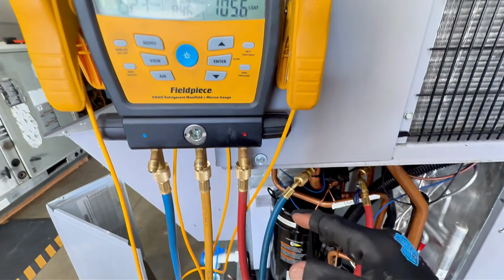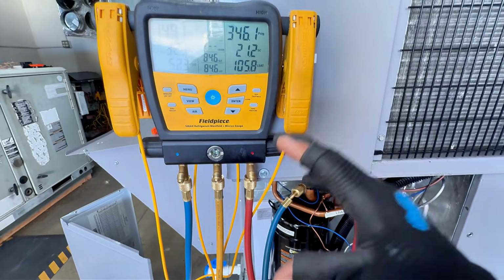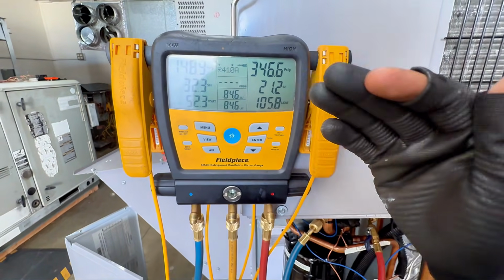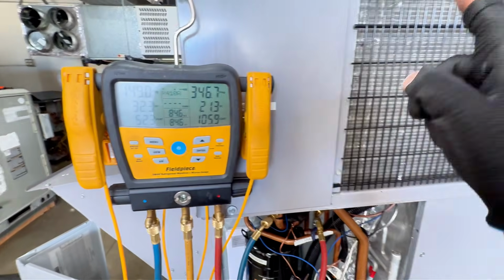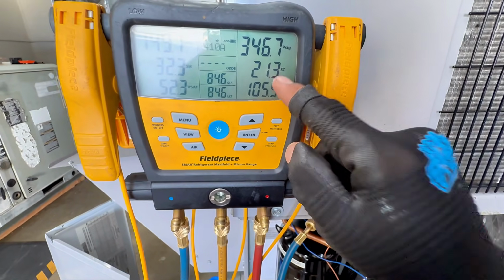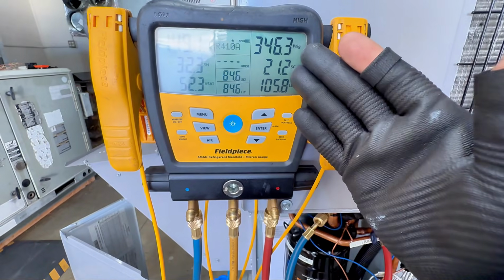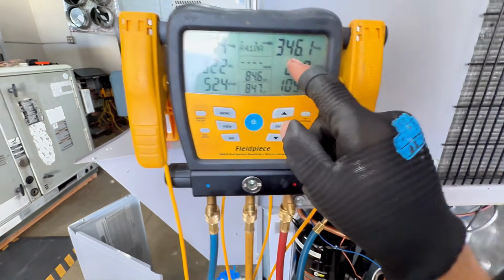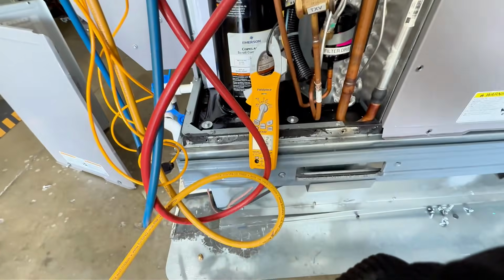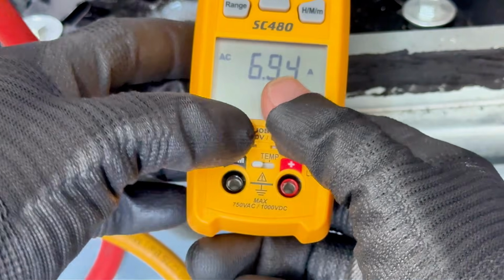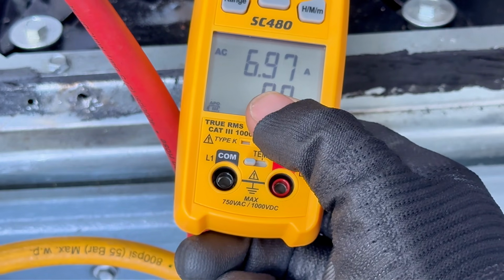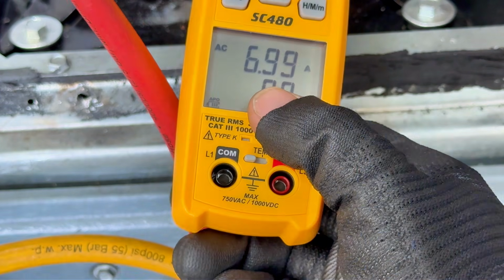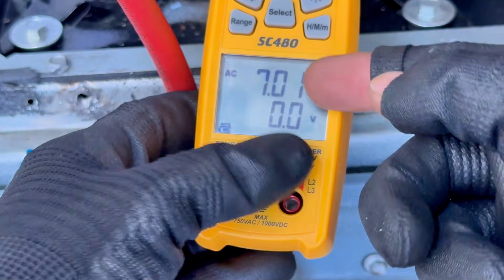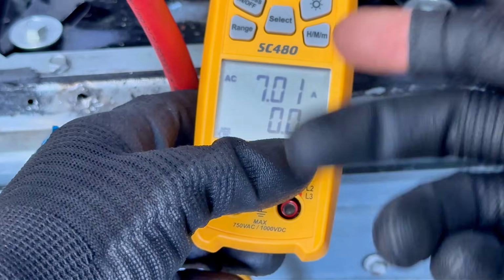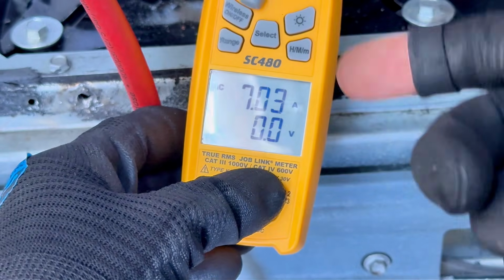So you want the compressor to work under its rated load amps, but it's so easy for it to go above those rated load amps by having a dirty condenser, and also by having the system overcharged. Right now I'm not talking so much about the diagnostics, checking superheat and subcool. It's just to show you that as the compressor has more refrigerant, I'm going to charge right now, 1, 2, 3, 4, 5, a couple seconds. If it has more refrigerant, it's pumping more. As it's pumping more, it's doing more work, more current.